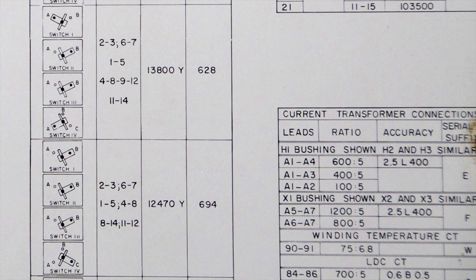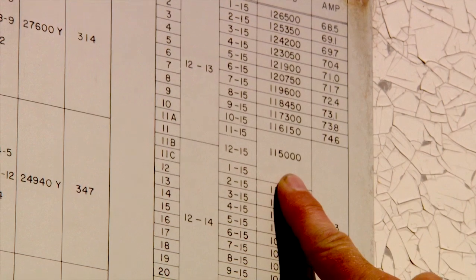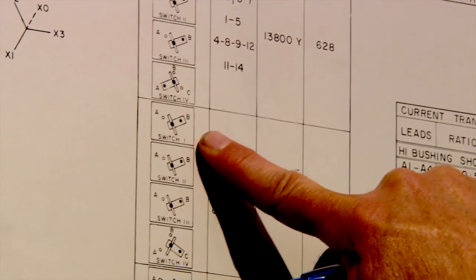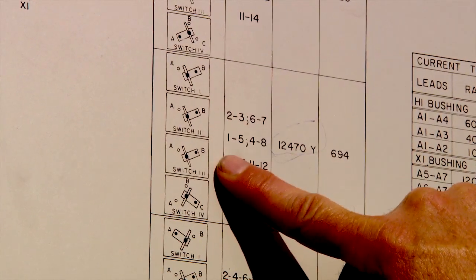The MUS offload tap should be set to whichever voltage option has a calculated ratio closest to the station transformer calculated ratio. This will ensure the greatest range of operation on the ULTC.